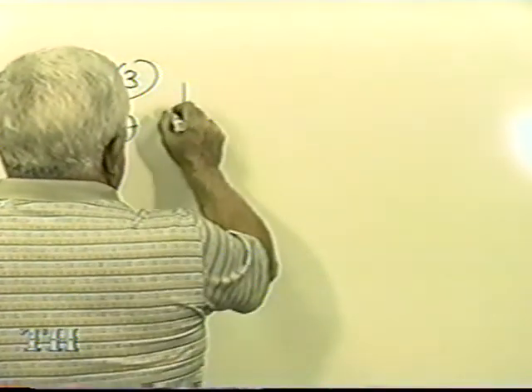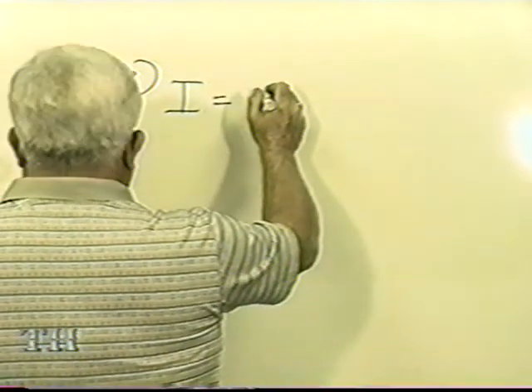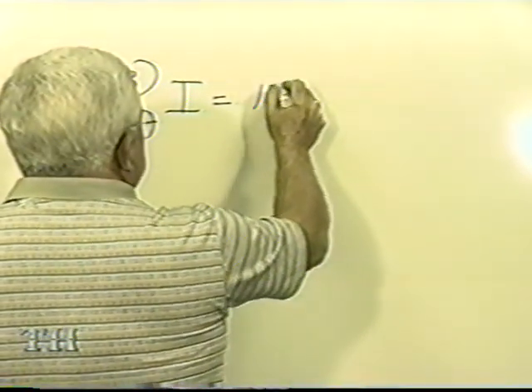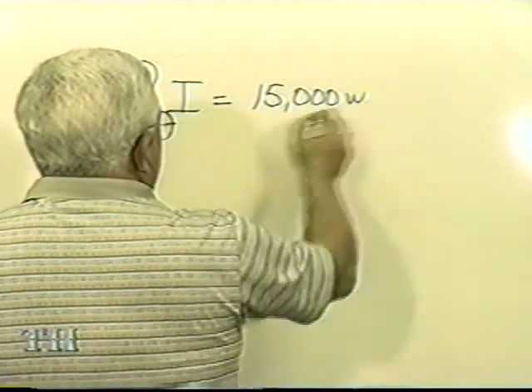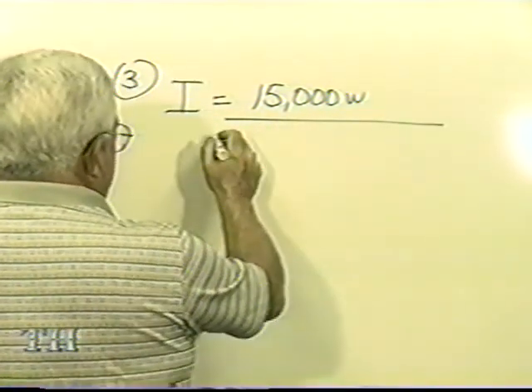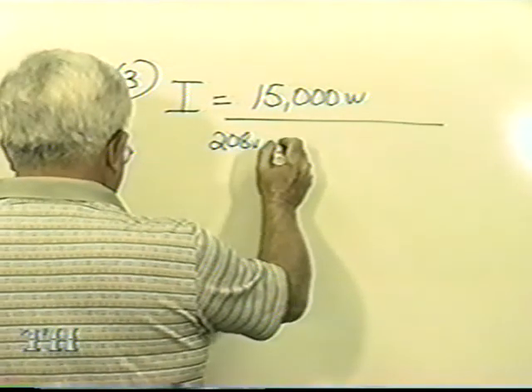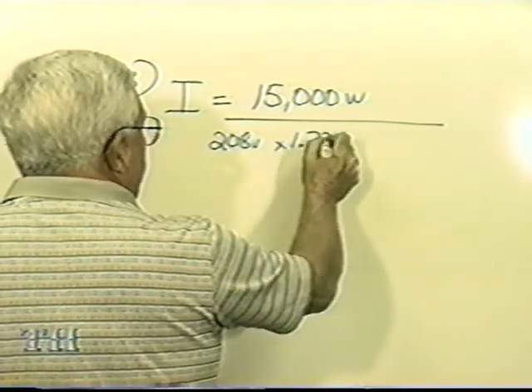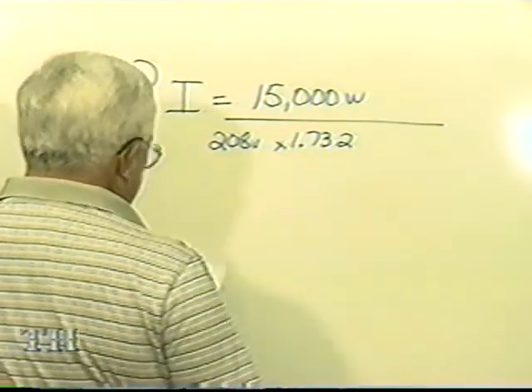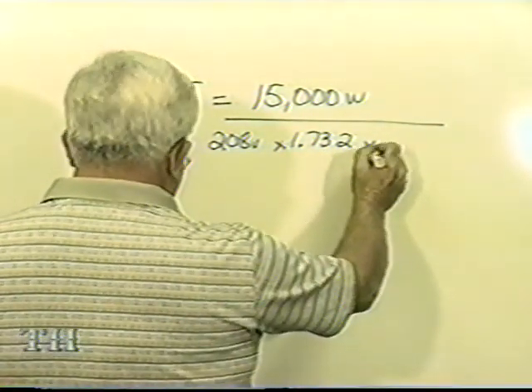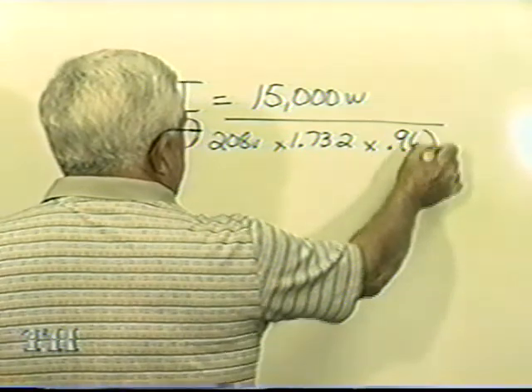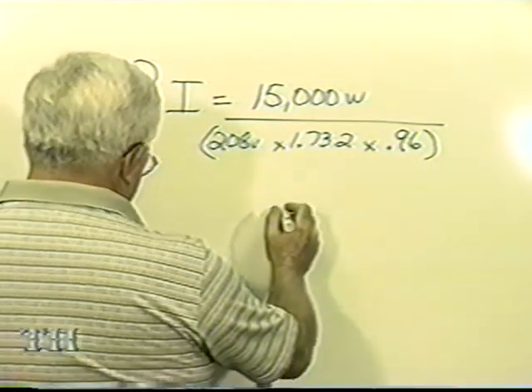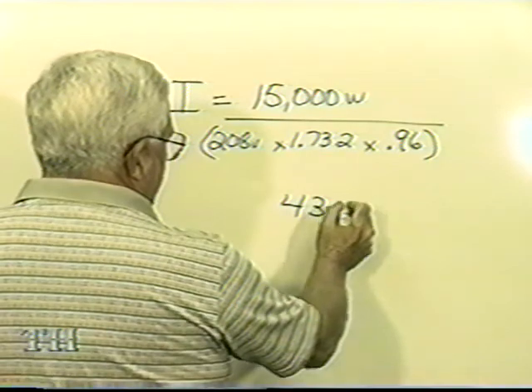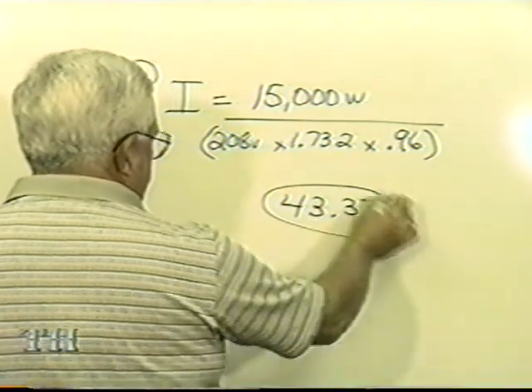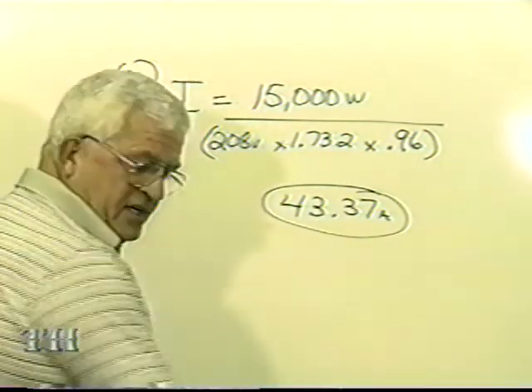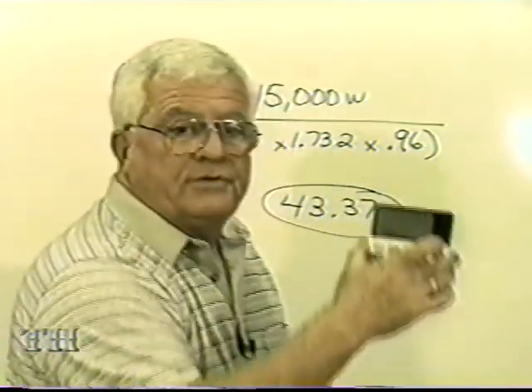They're looking for current. So I want to take the 15,000 watts and divide that by several things: 208 volts, it's 3-phase, and they're saying it has a power factor of 0.96. If I run that through my calculator, I'm going to come up with 43.37 amps as the answer. That's the current flow. Now, to work along with you, take your calculator.